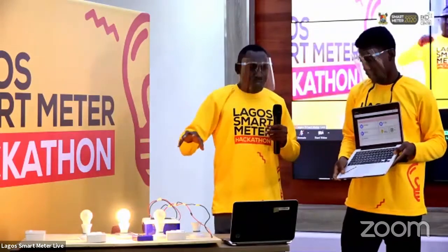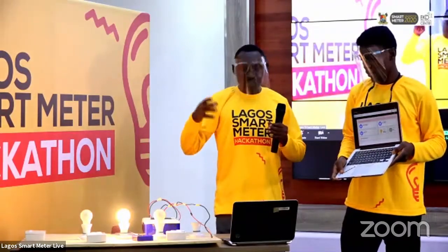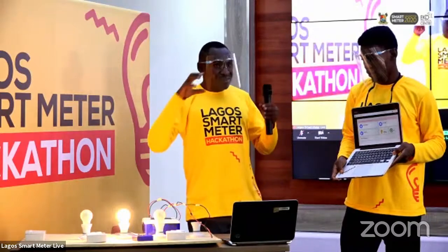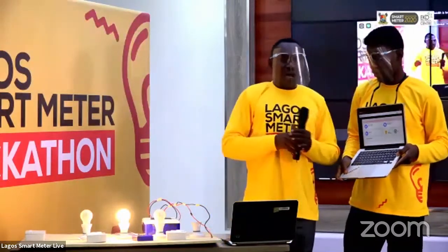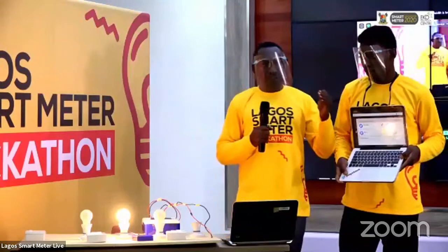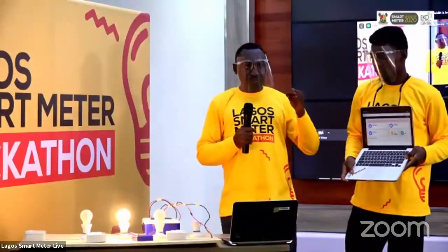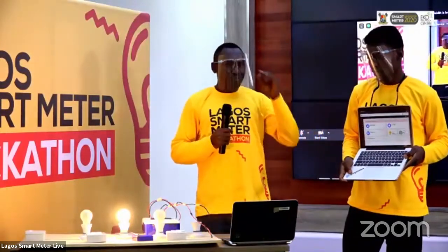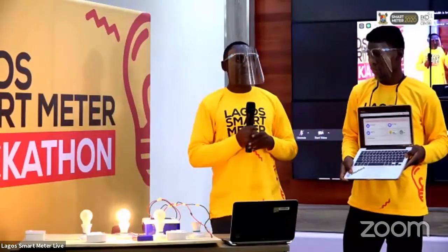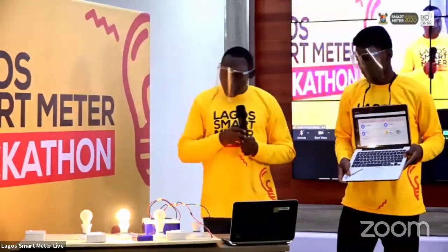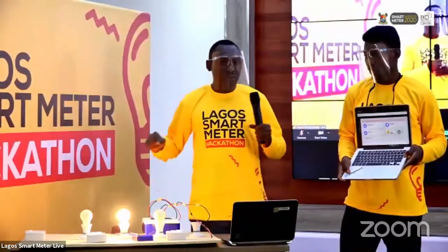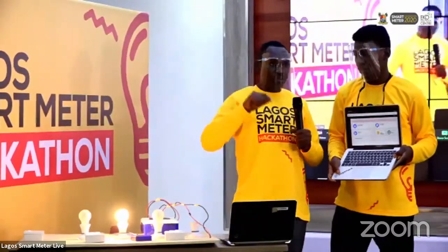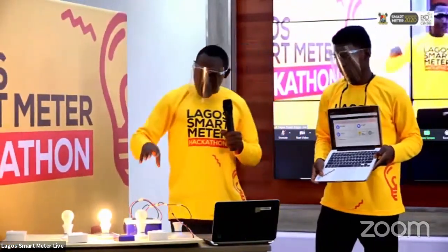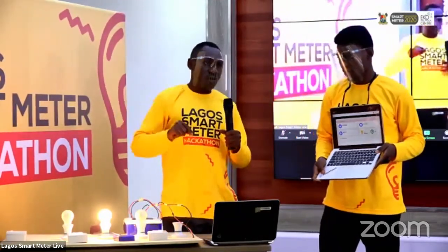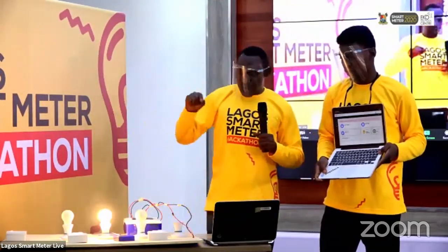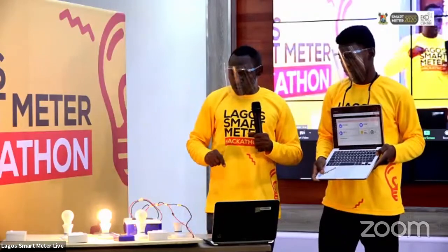That function is actually a GPS function - it captures the location of that meter. We have found out that with this last parameter, we can point out where bypass is occurring. Although it might not work on a single meter, because you need a network of meters for that to happen, with our algorithm we are able to identify where bypass is occurring. That's a key feature we have tried to solve in this competition.